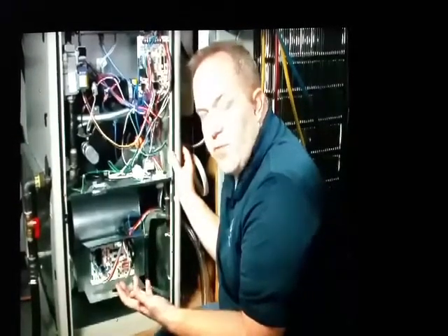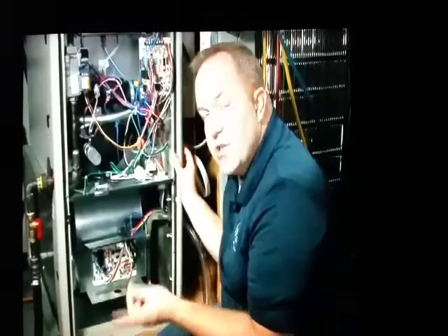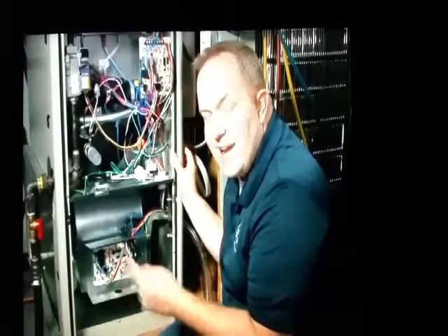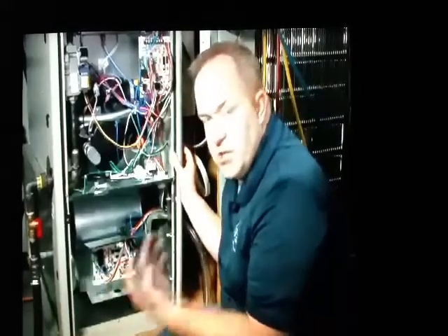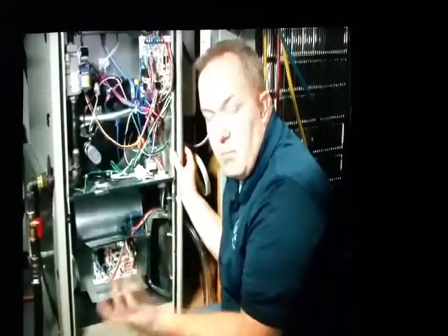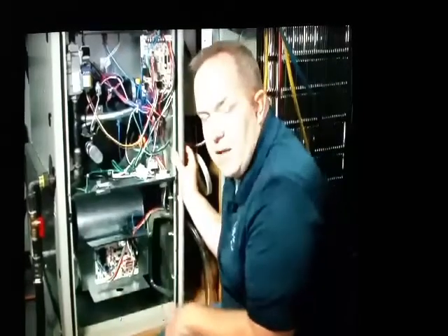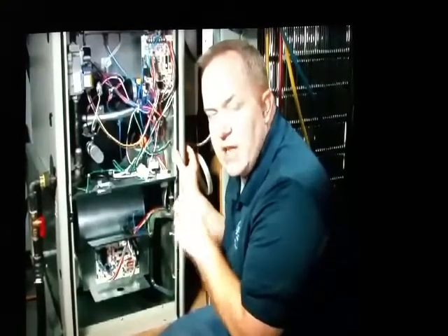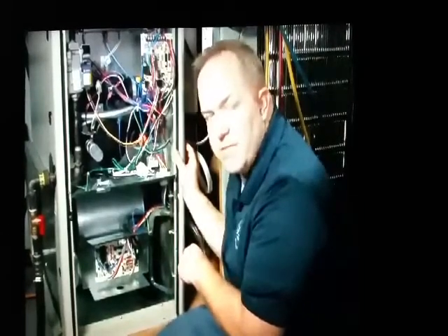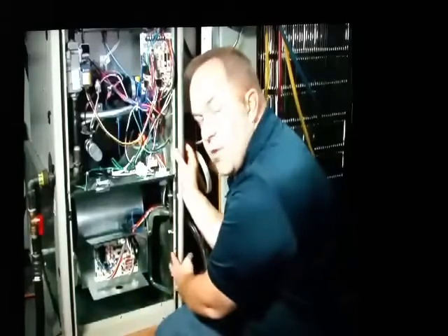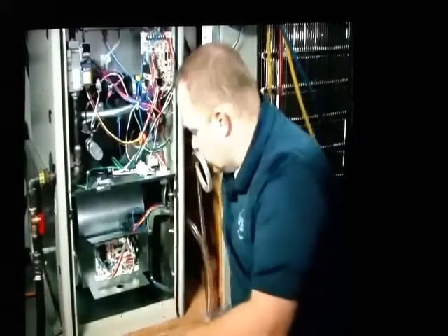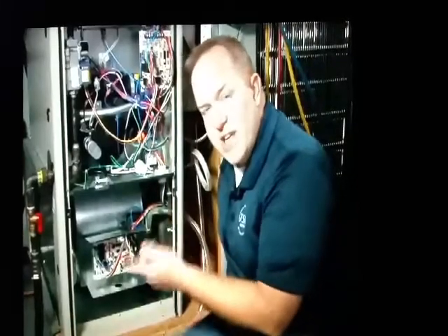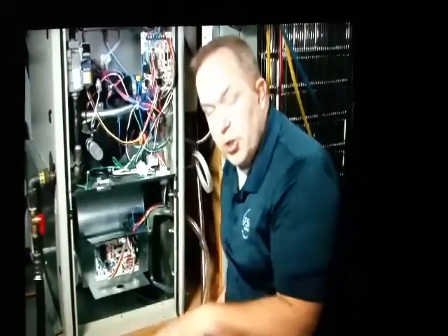We had done a prior video before about the effects of double trapping, specifically when you are attempting to incorporate a condensate pump. Condensate pumps just continue to grow in popularity in modern installations in homes that have high efficiency heating. It is too easy to inadvertently create a double trap scenario for a high efficiency furnace by using a condensate pump. You already have the one trap in the furnace. Now, if your tubing, if your plumbing goes into the well of that condensate pump and goes below the water line inside the well of that pump, there's your double trap. And it doesn't have to double trap for very long.